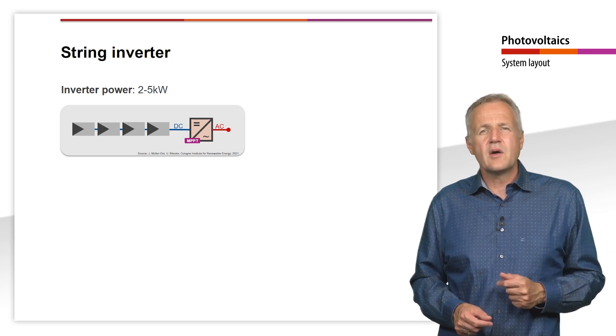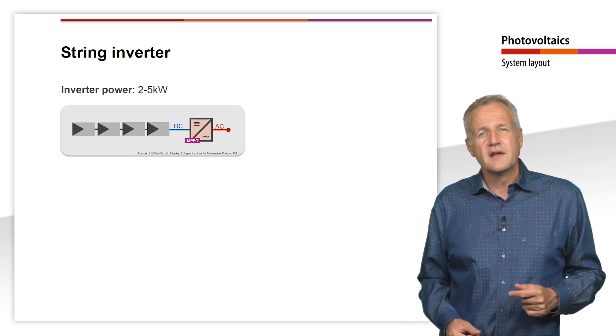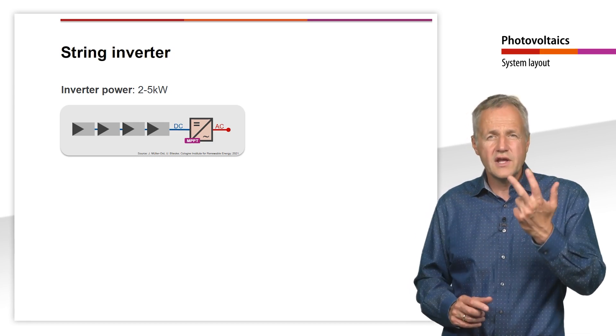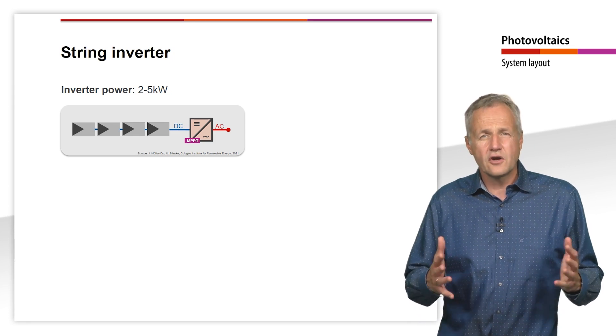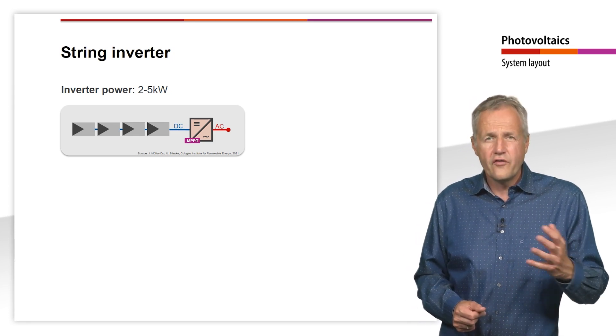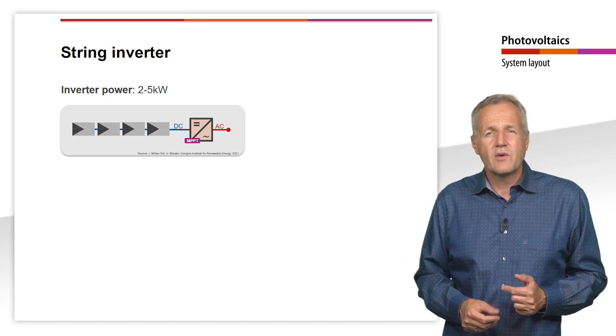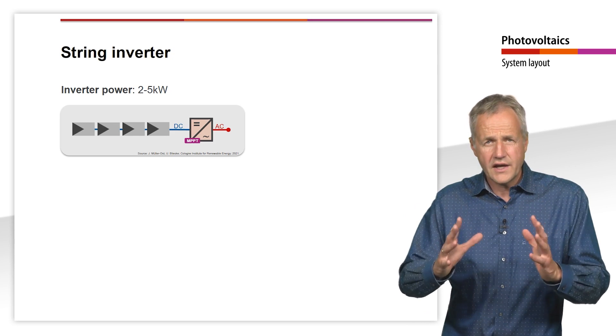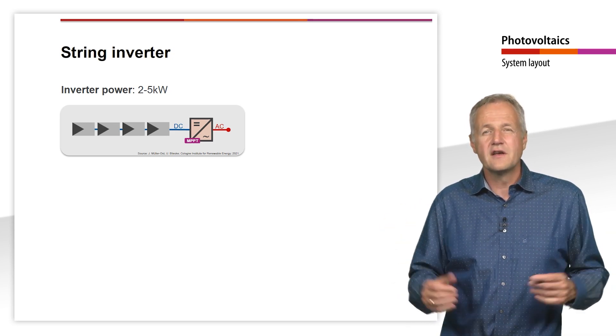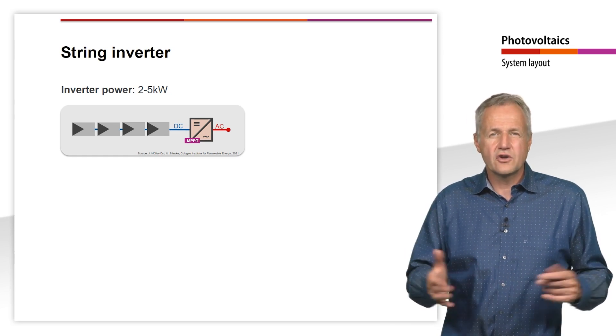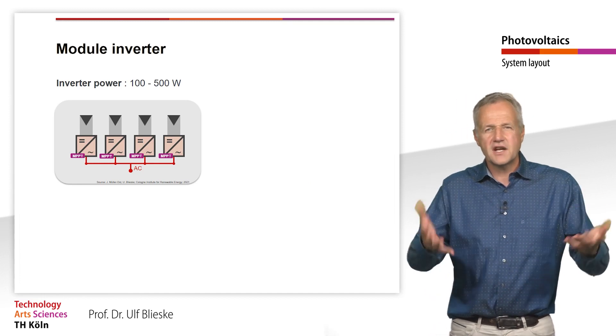A typical solar module has an MPP voltage of about 34 to 40V. Therefore, in very small systems with three or fewer modules, the critical voltage of 120V is not reached. So no further safety precautions need to be taken. As we have just seen, when planning a system with a string inverter, it is important to ensure that all modules of a string are oriented similarly and that no or only short-term shading occurs. If different orientations or shading cannot be avoided, it may be a good idea to use a module inverter.